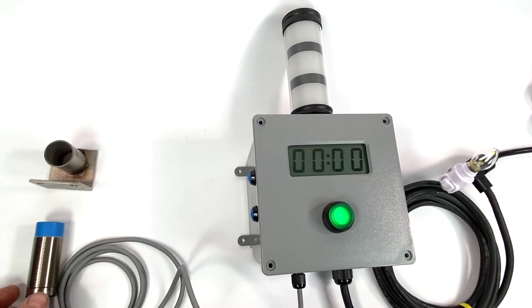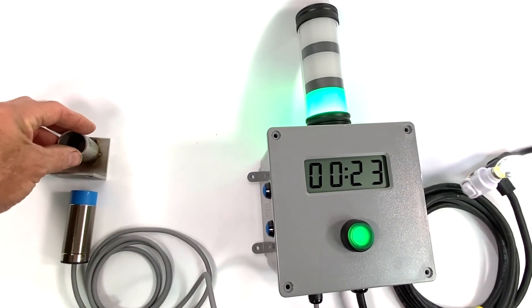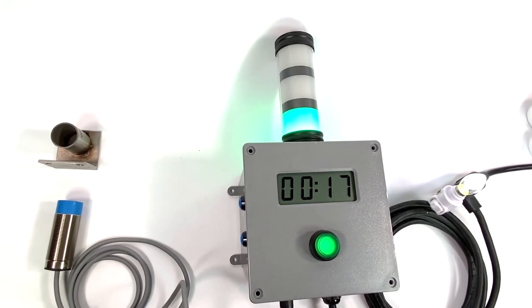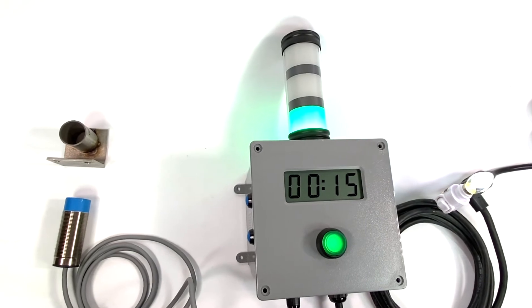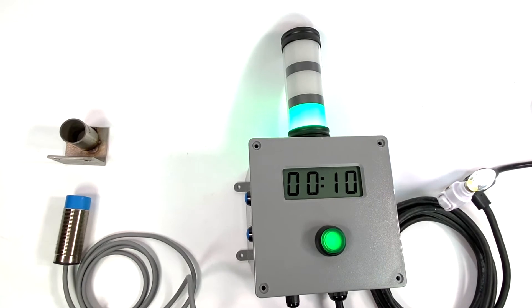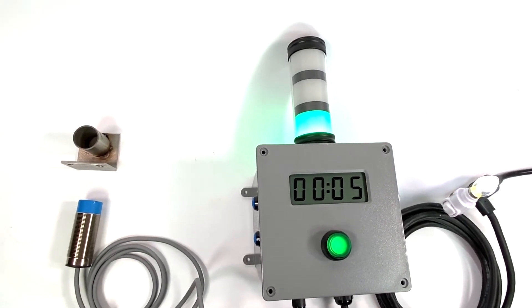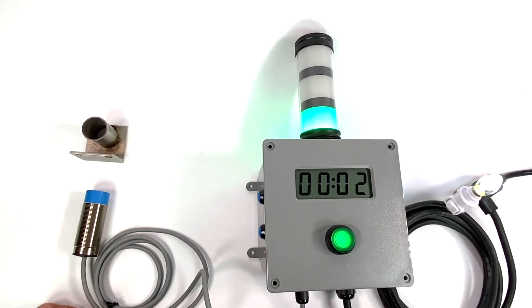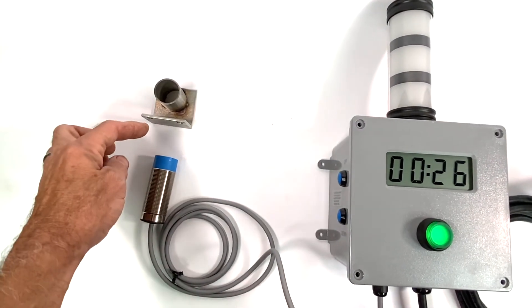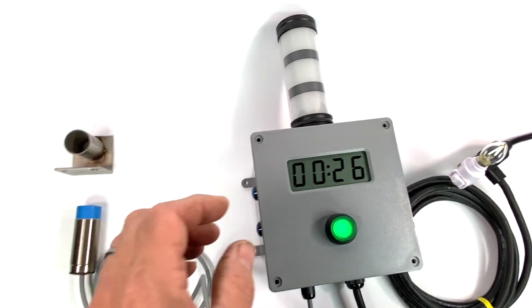Let's say we start a cycle, then for some reason the rack loses contact with the proximity switch. You get a special alarm before the end of the cycle and it's going to periodically remind you every few seconds that something's wrong with a chirp and the red light. Again, at the end of the cycle it's not going to alarm because the rack is already moved away from the proximity switch. That's the operation.